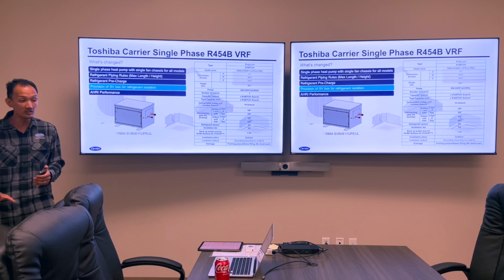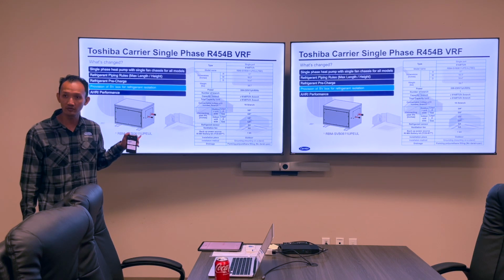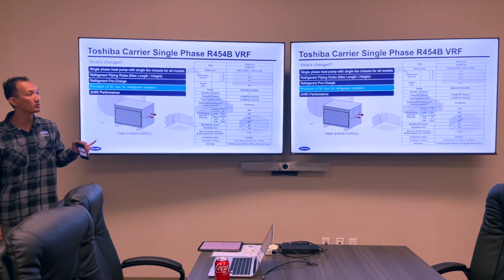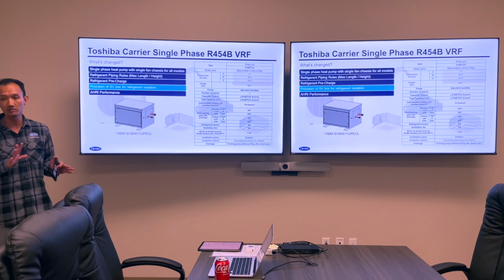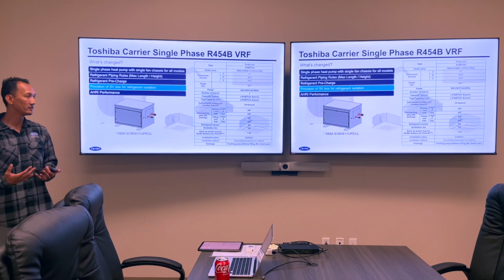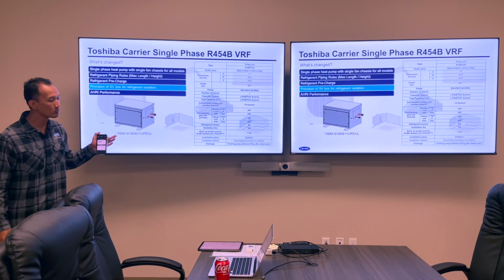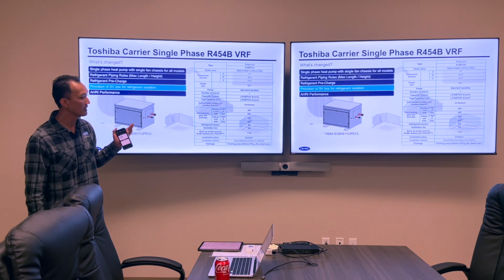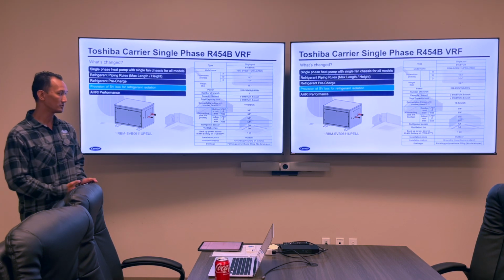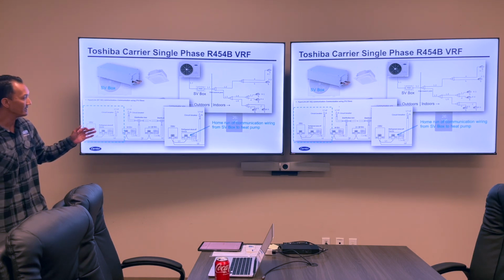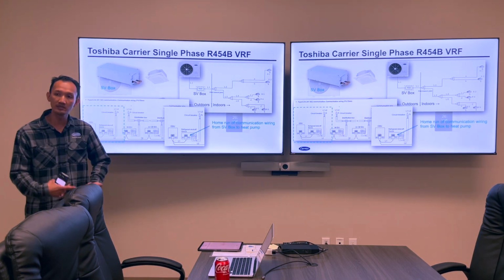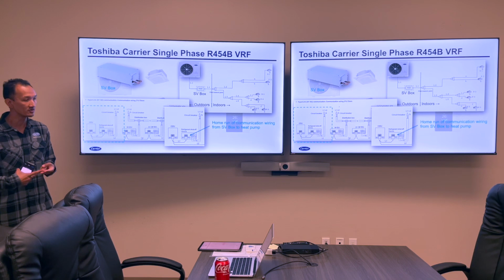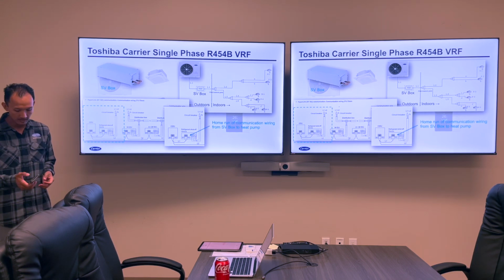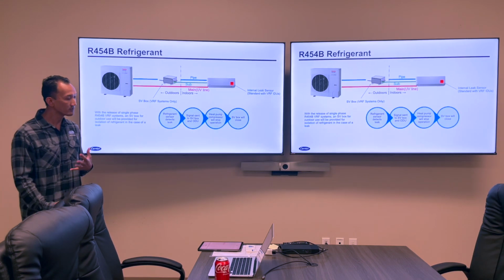I do want to stress that you won't necessarily need one of these for every project, but for those projects where you've got multiple fan coils or a lot of refrigerant in the system, this is one method for helping to mitigate releasable charge into a system. It's outdoor installation for now, but we are coming out with the 2nd generation version that you can install either indoor or outdoor. And all the logic is built in.